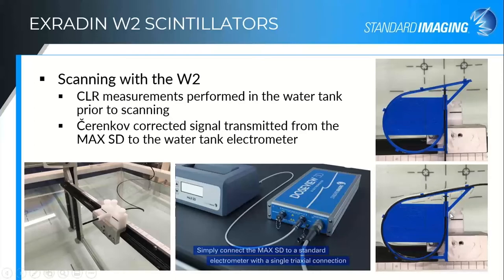We provide a jig that can be used for the CLR measurements in the water tank as well. This shows both the minimum fiber and maximum fiber configurations looking down at the water tank. You can also use a rectangular field method with it set up in the scanning position, as described in the user manual.